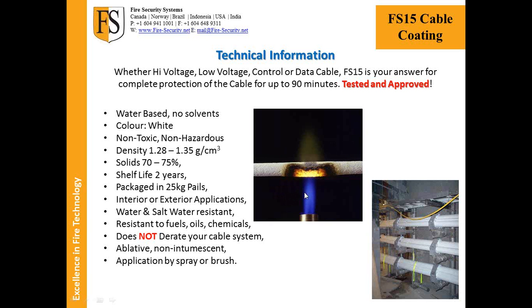The density of FS15 is 1.28 to approximately 1.35, so it's plus or minus, but I average it around about the 1.3 mark. What that really means is 1 litre of FS15 equals 1.3 to 1.35 kilograms. So 1 litre weighs 1.3 kilograms. And it carries a 70 to 75% solids value, so effectively 75% solids, 25% water.